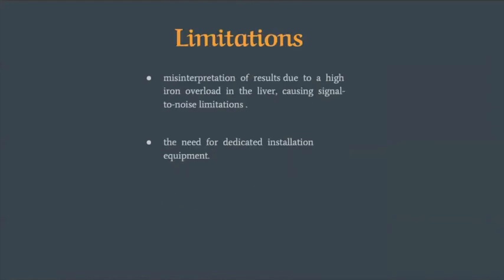Limitations: misinterpretation of results due to high iron overload causing signal-to-noise limitation. If the patient had higher iron overload, we can wait if the patient was under treatment. When the iron content decreases, we can do elastography; otherwise we can't do it. Also, the need for dedicated installation of this equipment. As we see, the driver, we have to buy this equipment; it is extra equipment, it doesn't come with the magnet, unlike ultrasound-based elastography. The ultrasound probe just needs the license for that program.